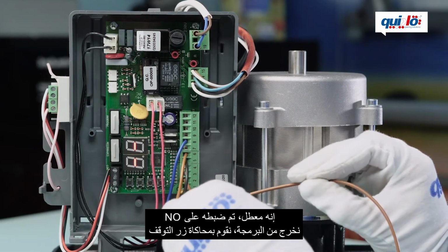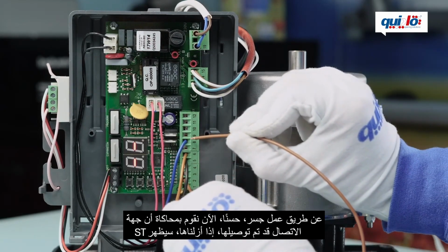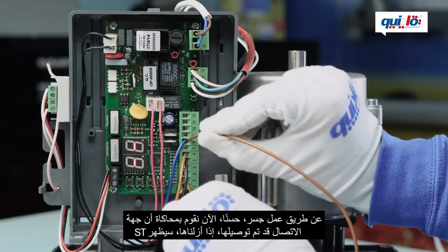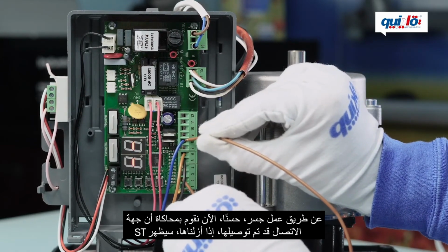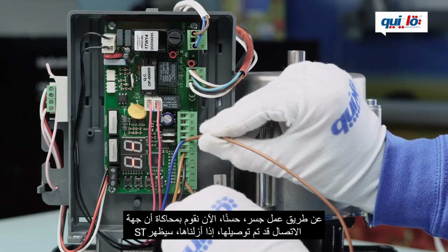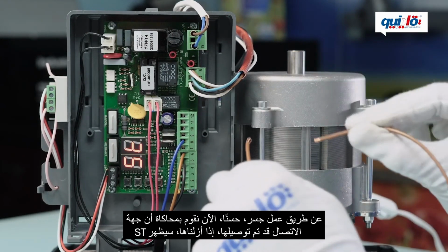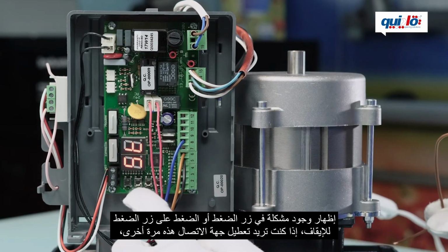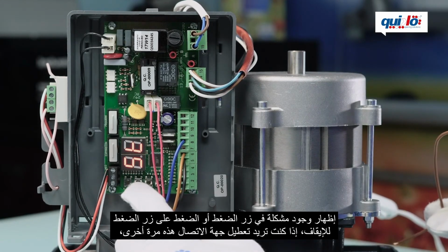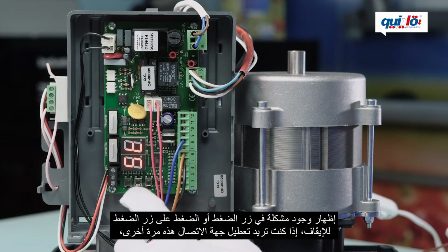We simulate the stop push button by doing a bridge, okay? Now we are simulating that the contact has been connected. If we remove it, the ST will appear to show that there is a problem with the push button or the push button of the stop is pressed.